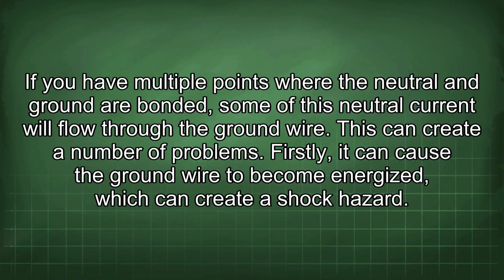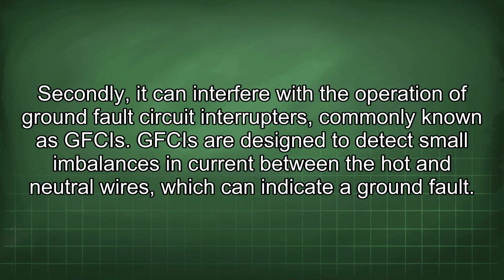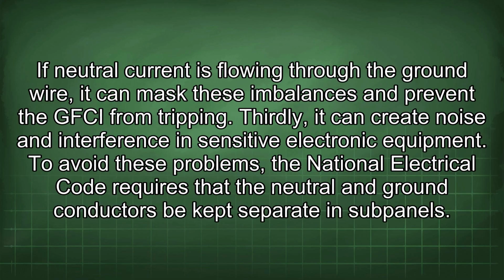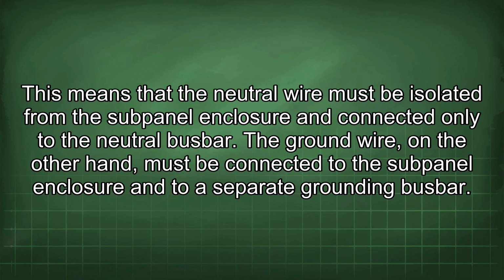Firstly, it can cause the ground wire to become energized, which can create a shock hazard. Secondly, it can interfere with the operation of ground fault circuit interrupters, commonly known as GFCIs. GFCIs are designed to detect small imbalances in current between the hot and neutral wires, which can indicate a ground fault. If neutral current is flowing through the ground wire, it can mask these imbalances and prevent the GFCI from tripping. Thirdly, it can create noise and interference in sensitive electronic equipment. To avoid these problems, the National Electrical Code requires that the neutral and ground conductors be kept separate in subpanels. This means that the neutral wire must be isolated from the subpanel enclosure and connected only to the neutral busbar.